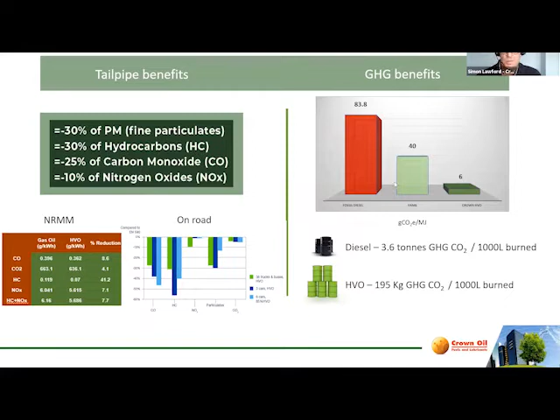Now, HVO is relatively new to the UK market, but not as new as people might think. The fuel is old enough to have been included in international fuel standards - it's an EN 15940 paraffinic fuel, and it also meets ASTM D975, the US diesel standard. The difficulty is that it doesn't meet EN 590, though it meets that spec in all aspects apart from density. Annoyingly, the density of EN 590 is higher than HVO because of the aromatics, the nasties, that mineral diesel has. So we're not able to meet the ubiquitous spec because our fuel is cleaner and less toxic to the environment and to people.